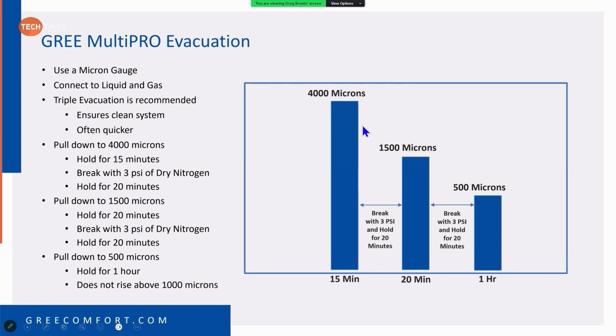Now you've done 2 things to ensure you don't have any leaks. You have done a nitrogen pressure test of 500 pounds for an hour to ensure you don't have any leaks, and you also did a triple evacuation, which means you've got a good, clean, dry system, and you also made sure it held 500 microns for at least an hour.